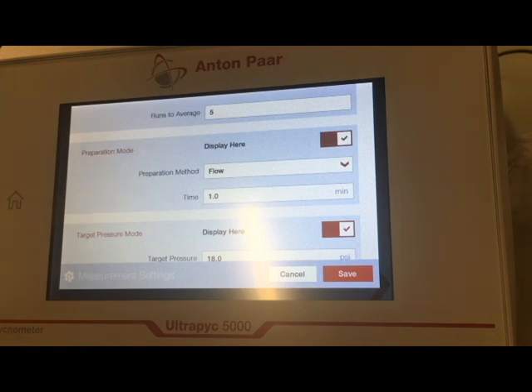Preparation mode. This is how the gas flows into the cells. Flow is to be selected if you have a solid or if you are using the micro, meso, or nano cells. Typically this ranges between 1 and 3 minutes. If you are trying to analyze a more porous sample, you're going to choose 3 minutes rather than 1.